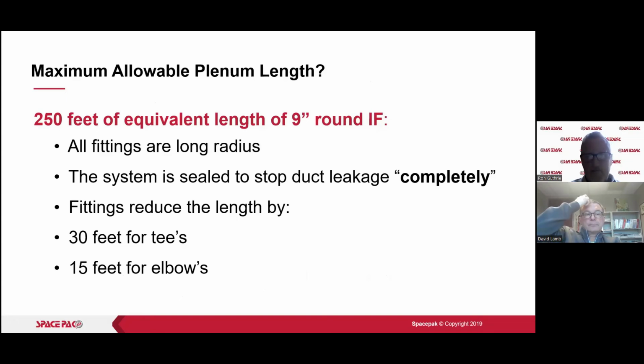All right, again, I talked about this 250 feet of equivalent length of 9-inch round, if all fittings are long radius and the system is sealed to stop duct leakage completely. So it has to be a sealed system. And if you're going to use standard galvanized pipe, you have to seal every seam, every joint, and every seam in a 90-degree elbow as well. Plus, you're not going to find long radius elbows in standard galvanized pipe. Fittings reduce the length by 30 feet per tee, 15 per elbow. This is a long radius elbow, so again, use 30 feet for a short radius elbow, and work backwards from 250 feet, and that'll give you the maximum length.